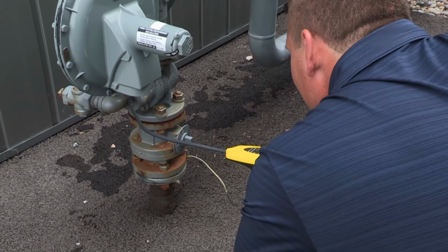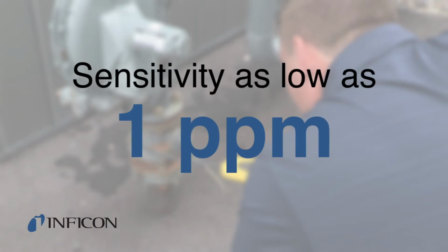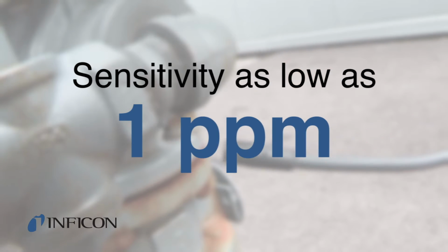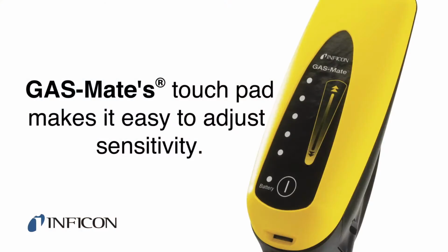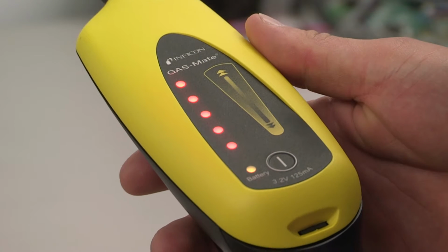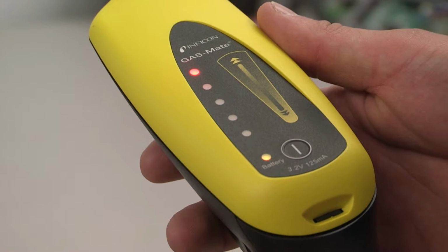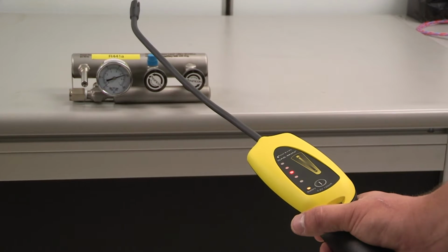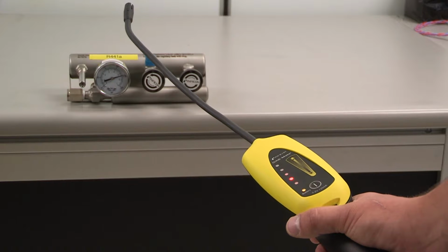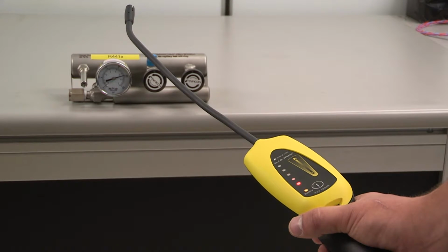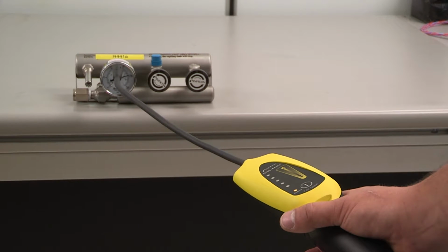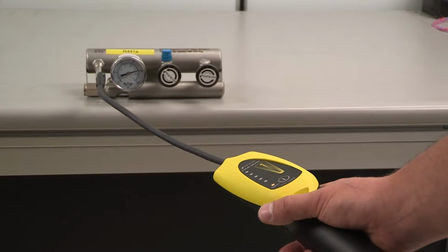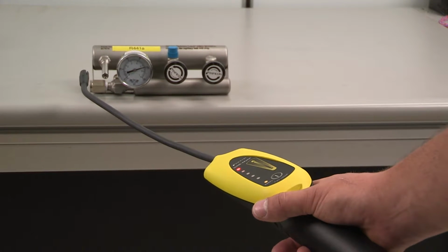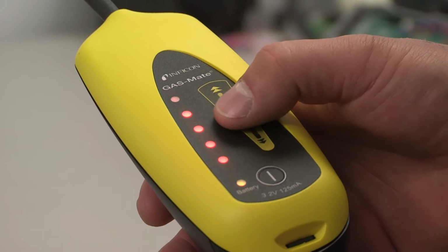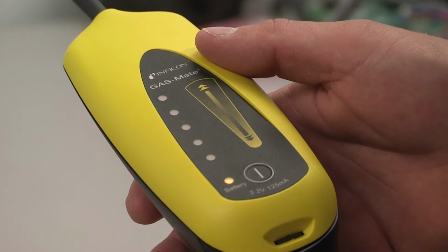And when you think you don't have a leak, think again. With sensitivity as low as 1 part per million, you'll find very small leaks. That's accuracy. GasMate's touchpad makes it easy to adjust sensitivity for different situations. Start by powering on the leak detector and make sure GasMate is set to high sensitivity mode. After a short warm-up, you can begin leak checking. The LED lights signal the intensity of the leak. When the leak is discovered, switching to low sensitivity helps pinpoint the leak source.